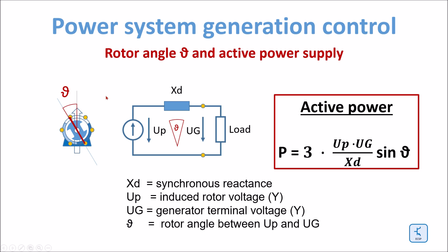Here we have a simplified model of a three-phase generator — this is a single-phase model. Here we have the induced voltage in the generator, then we have a synchronous reactance inside the generator, which are the generator coils mainly. Here we have the terminal voltage of the generator. In between the terminal voltage and the induced voltage we have this so-called rotor angle. The rotor angle between UP and UG is the same angle as the angle between the axis of the rotor and the rotating magnetic field in the three-phase coils.